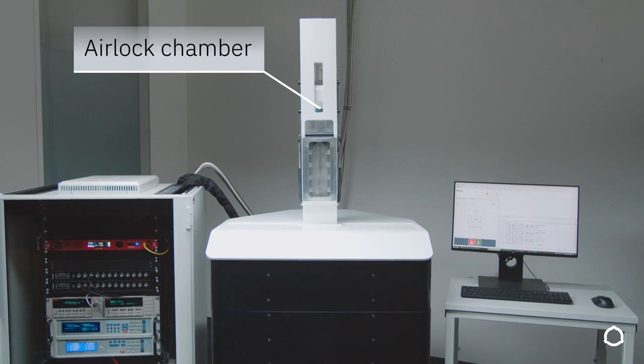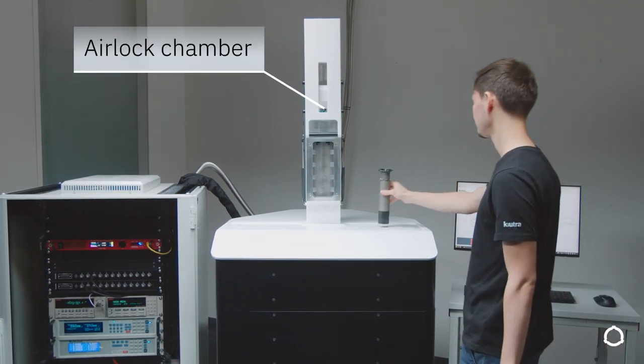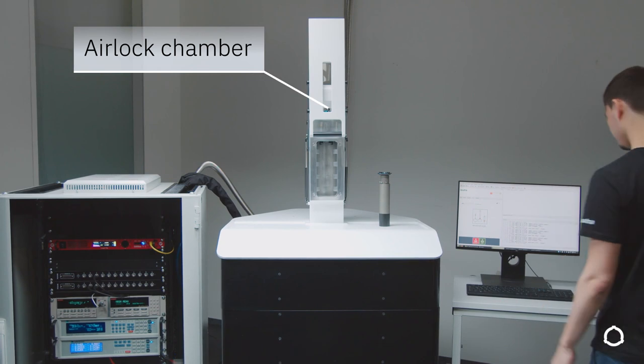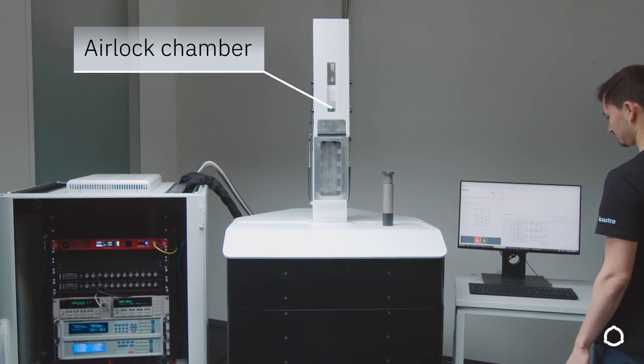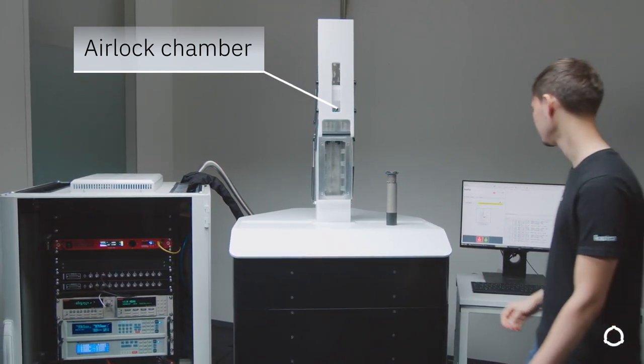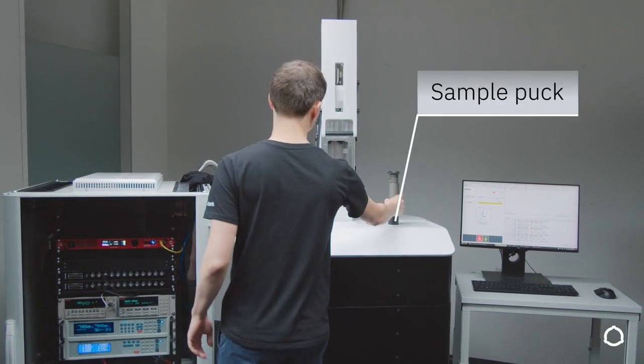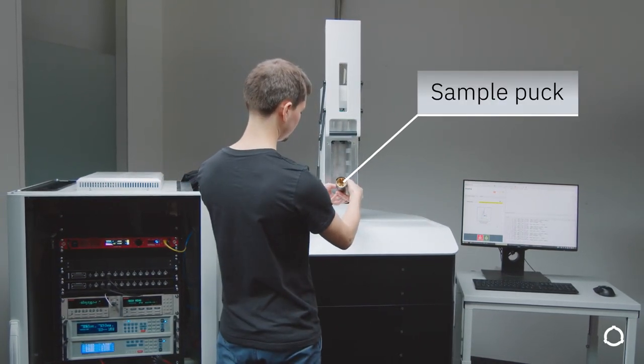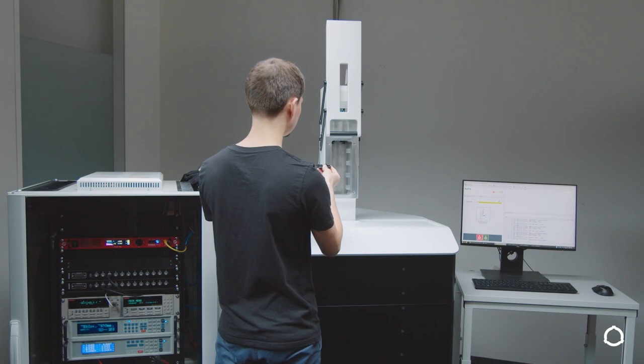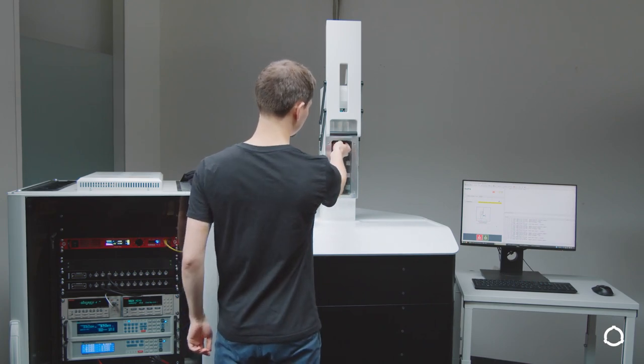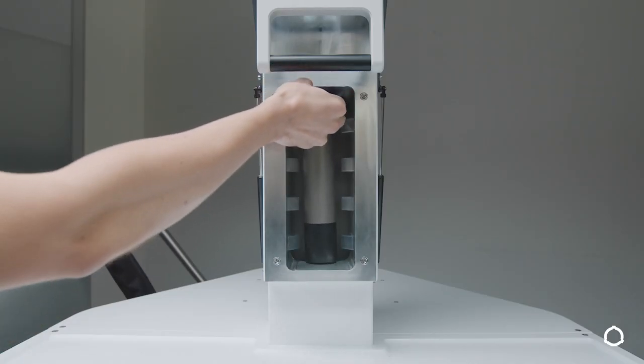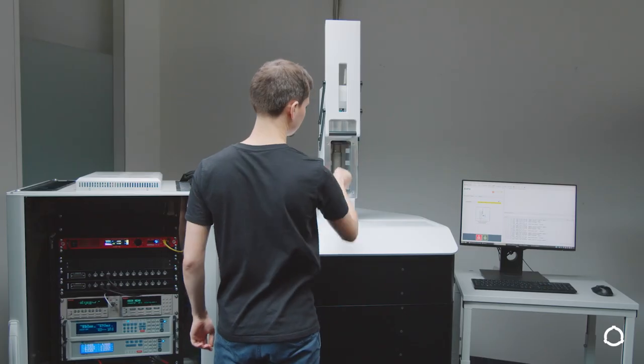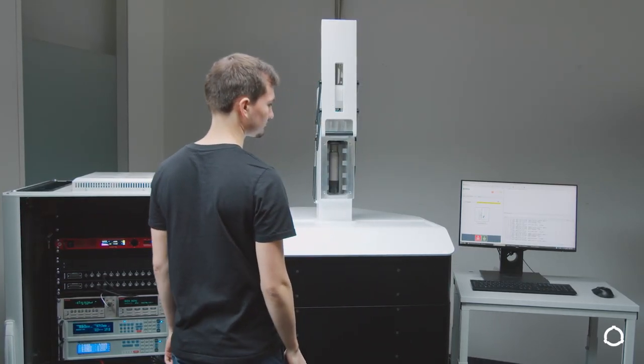The automatic sample loading process can be started in our instrument control software with a few clicks and guides the user through the sample loading process. First, we make sure that the puck is secured in the transfer cage. Then the transfer cage is inserted into the vacuum lock. The automatic gas handling system starts the pumping process and the door can be closed as soon as it is indicated by the software.